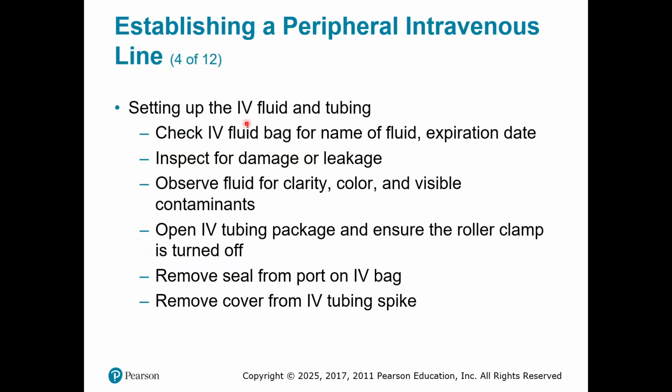Setting up the IV fluid and tubing. You want to check your IV fluid bag for the name. You want to check it for the expiration date. Make sure it's not damaged or leaking. You'll make sure the clarity of the fluid is what it's supposed to be. You're going to open the IV tubing package, ensure the roller clamp is turned off.